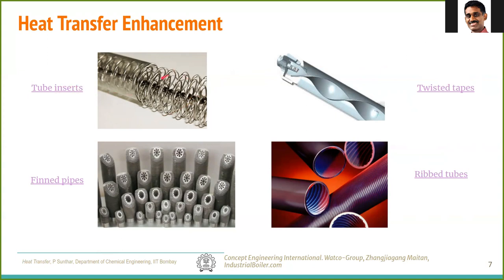The first method is tube inserts — a spring-like structure inserted inside the tube that touches the outer wall. Being metallic, this insert gets heated to roughly the same temperature as the tube surface. When liquid passes through, it has a larger surface area of contact. This acts like an extended fin, transporting heat from the surface to an increased effective surface area.